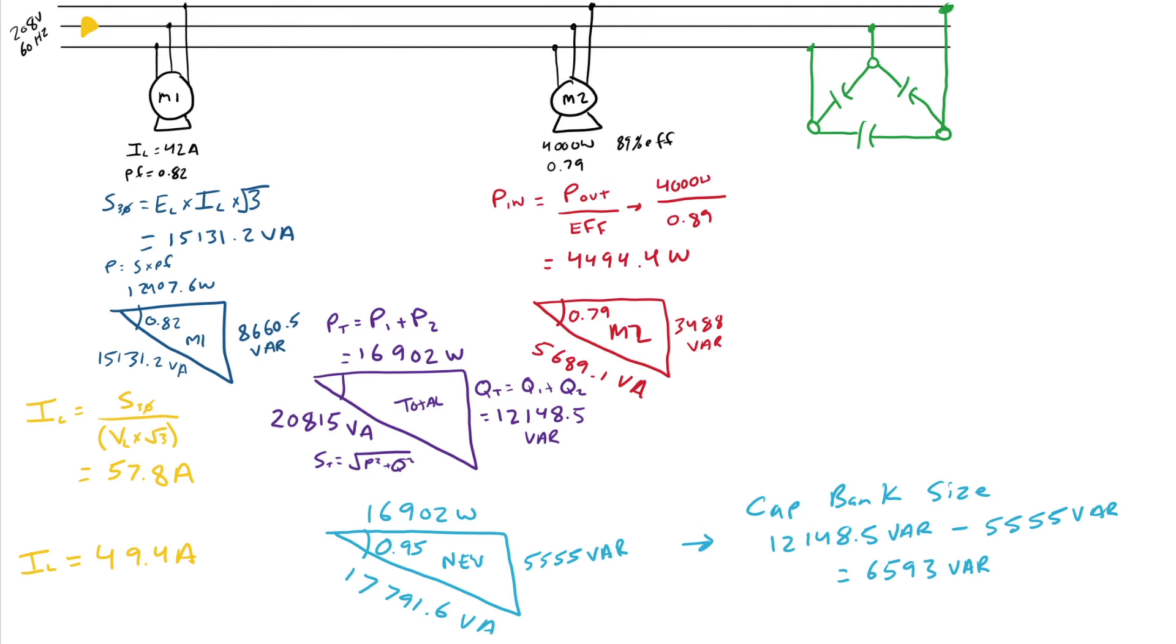Keeping in mind, with a capacitor bank, because it is purely capacitive, my VARs equal my VA. Or, my S equals my Q. So, now that I know how big the size of the required delta capacitor bank needs to be, 6,593 VARs. I want to break it down a little bit more, though. I want to break it down into the actual capacitance.